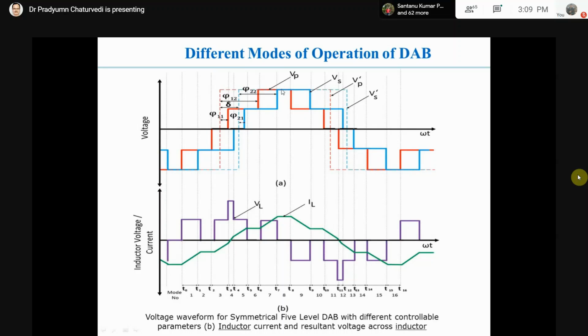Now in the same way, you can see this blue line for secondary voltage across the HFT, the secondary dotted line. This is the fundamental secondary voltage, or you can say the 2-level square wave voltage in an ideal condition in a traditional 2-level converter. We have to compare its performance with the traditional 2-level converter, that's why we are using this as the base or reference. Again in VS you can see this blue line, the top one, from level 1 to level 2, level 3, level 4, level 5. So 5 labels.